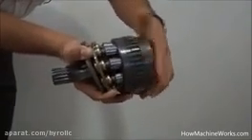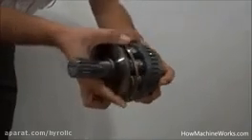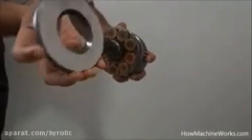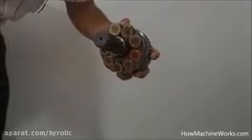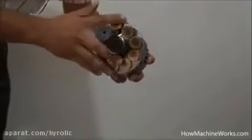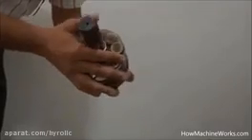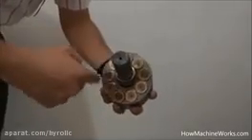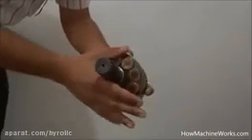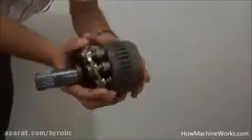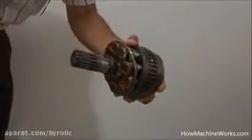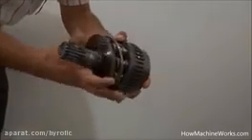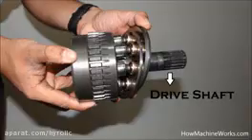So when the swash plate is vertical, there is no flow, and as the swash plate angle changes, the flow varies depending upon the angle of the swash plate, and the swash plate angle is controlled by a valve according to the load and the requirement. So that's the rear side of the piston, which is sliding over the swash plate over there. Okay, now let's go and have a closer look and identify each component.